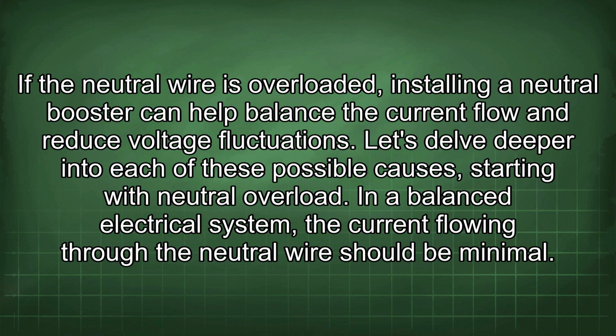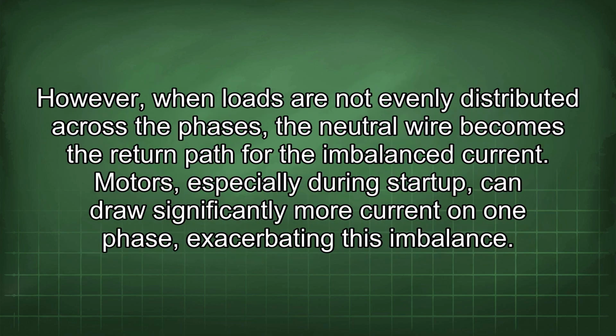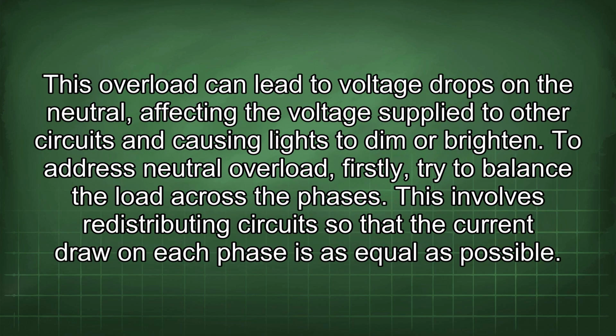In a balanced electrical system, the current flowing through the neutral wire should be minimal. However, when loads are not evenly distributed across the phases, the neutral wire becomes the return path for the imbalanced current. Motors, especially during startup, can draw significantly more current on one phase, exacerbating this imbalance. This overload can lead to voltage drops in the neutral, affecting the voltage supply to other circuits and causing lights to dim or brighten. To address neutral overload, firstly try to balance the load across the phases.